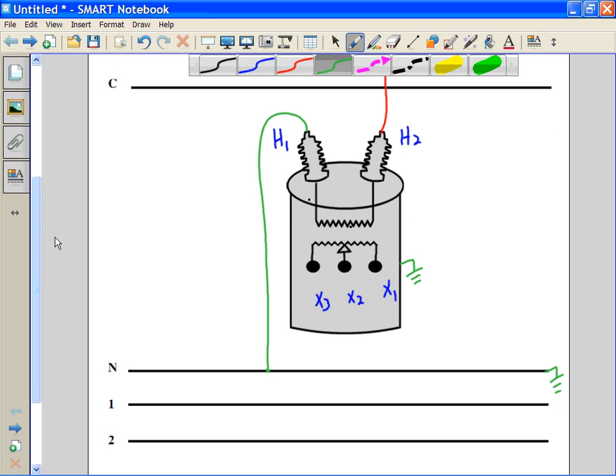And that will take care of our primary connection. The secondary connection is a 3-wire connection, which means we need to connect from the transformer to 3 different wires on the secondary system. So the X2 in this case will be the neutral, so we'll bring that down to neutral. And then X3 can come to either line 1 or line 2. It doesn't matter which one you bring it to. X1 will go to the other one, in this case line 2.